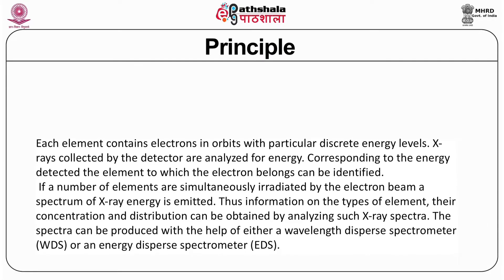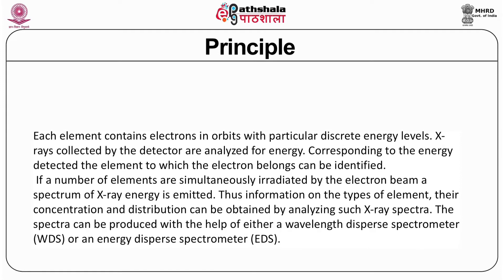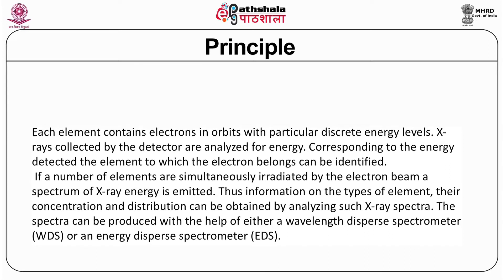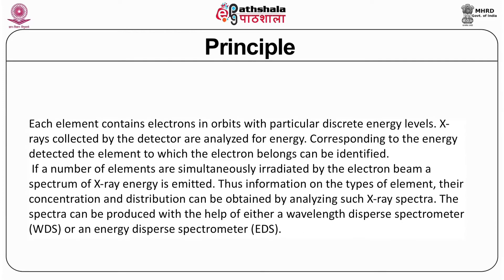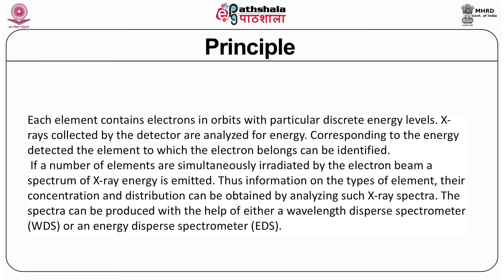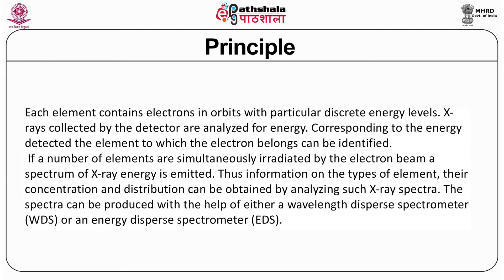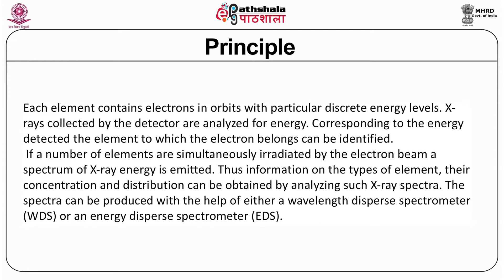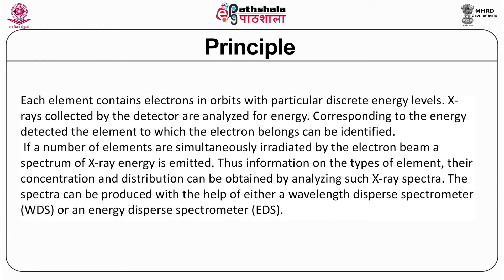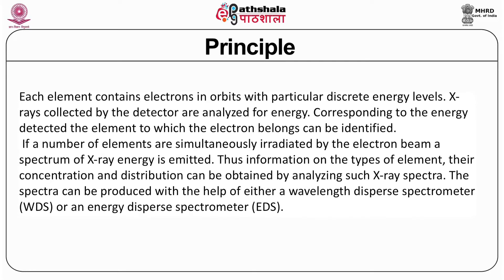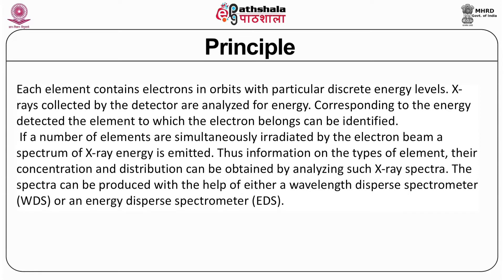Each element contains electrons in orbits with particular discrete energy levels. The X-rays collected by the detectors are analyzed for different energies, and the element to which each electron belongs can be identified. If multiple elements are simultaneously irradiated by the electron beam, a spectrum is generated with X-ray peaks at different energy levels. Information on the types of elements and their concentration distribution can be obtained by analyzing the X-ray spectra. The spectra can be produced with either a wavelength dispersion spectrometer (WDS) or an energy dispersion spectrometer (EDS).